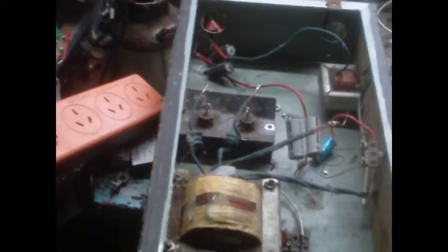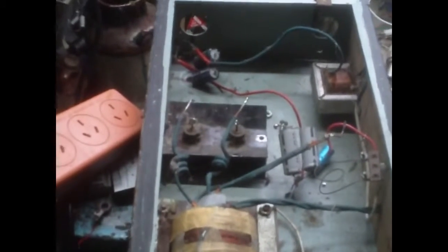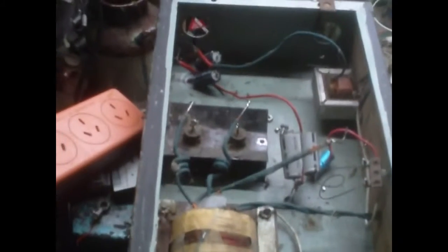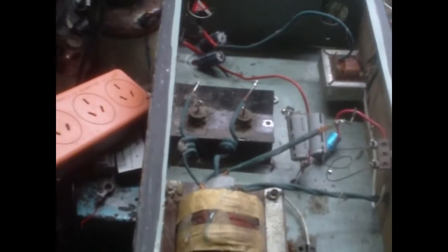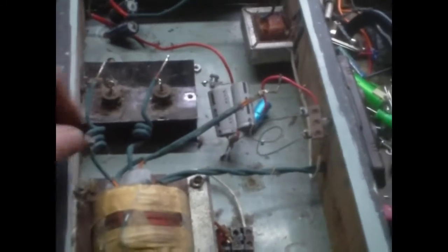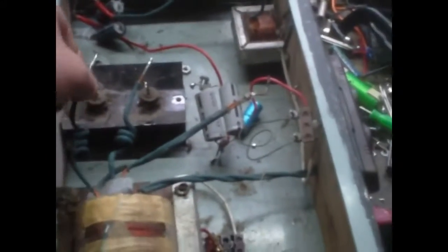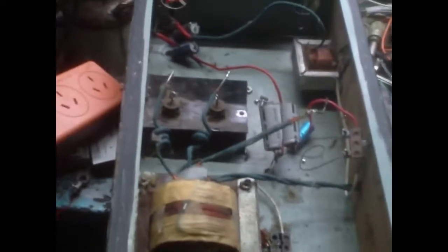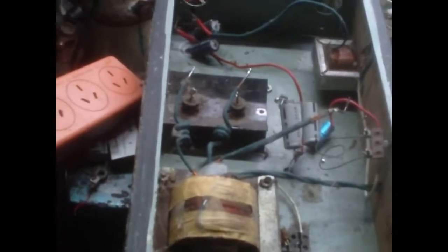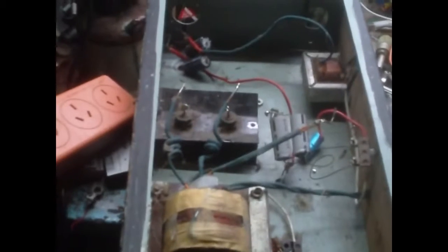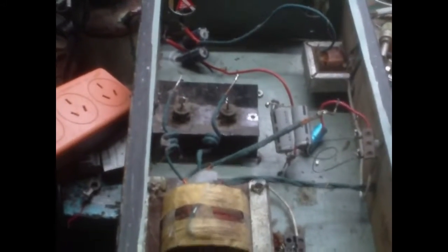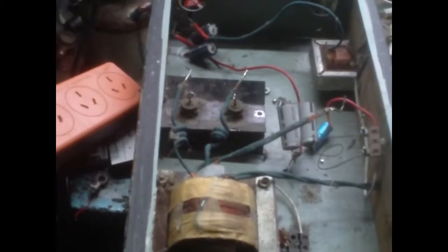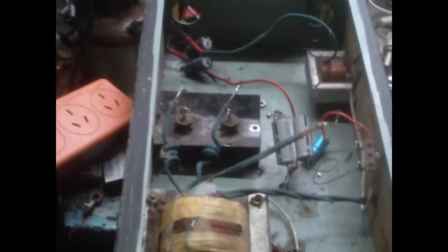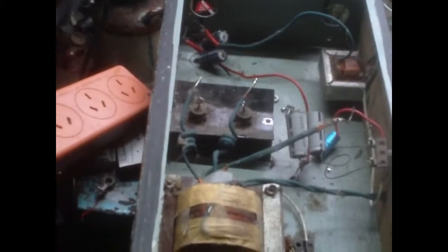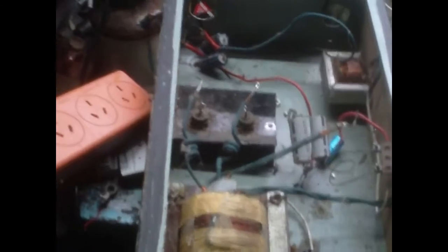One thing I'm increasingly believing when running smallish generators is that power factor is incredibly important. In other words, if your power factor is crap, you're going to overload and wear out your generator, whether you're overloading it in terms of wattage or not. That's why they rate generators in volt-amps and not watts. When you have a 1.1 kVA generator, that's the maximum volts times amps you can draw from it, whether that's only producing 800 real watts or not, you know what I'm saying.